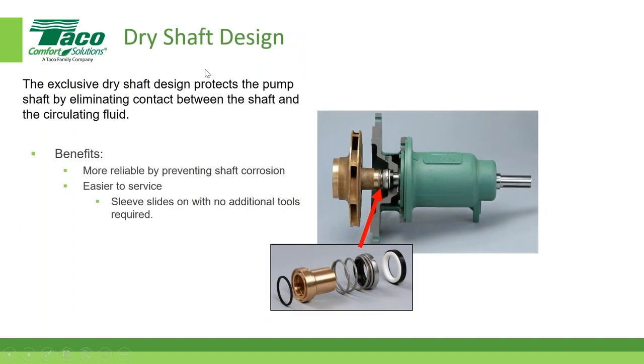Pretty good. Dry shaft design. So here's that bearing frame. I think we have five or six different sizes based on the requirements. The dry shaft design protects the pump shaft by eliminating contact between the shaft and the circulating fluid. It makes sense, right? The water is on the left side, and on the right side there's no water getting into that area.